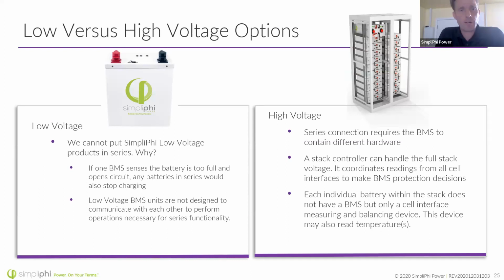What do we offer in terms of batteries at SimpliPhi? We have both low and high voltage options, right? Our Briggs & Stratton batteries start out at 12 volts. We have small batteries at 12 volts. We have larger batteries at 24 volts, and there are still many legacy pieces of equipment that are using 24 volts. Typically, mobile applications use 12 or 24 volts still, and so we do make some batteries in the 24 volt range. The most common, and really the industry standard for home battery backup, is 48 volts, and we have a variety of options in 48 volts that we'll get into. I'm showing the AmpliPHI battery here. It has closed loop communications as well as a device port to communicate to different devices through CAN bus. And we have many options there for our 48 volt that we'll talk about.